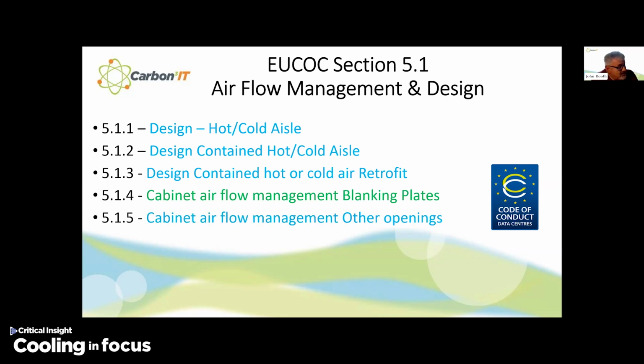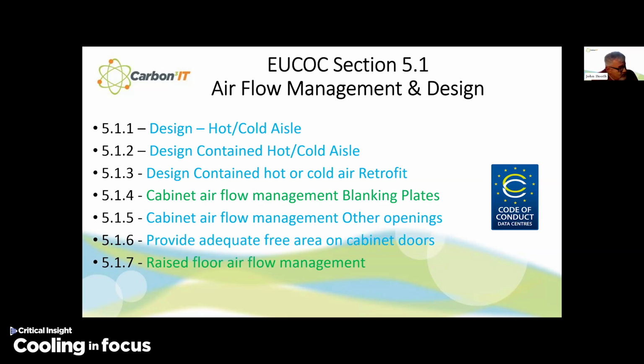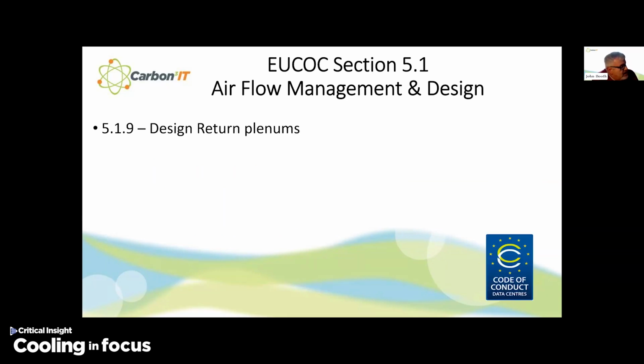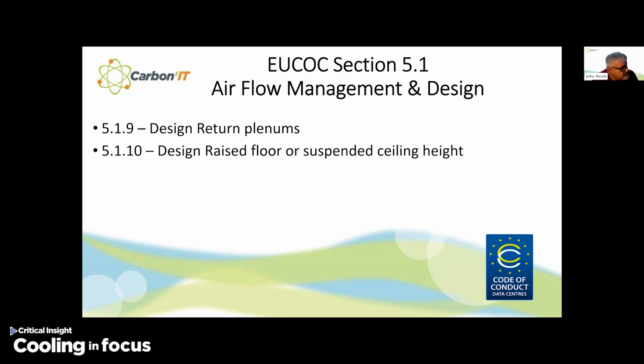Cabinet airflow management for other openings in your floor. Provide adequate free area on cabinet doors. Raised floor airflow management, and then raised floor airflow management in terms of obstructions. Design return plenums. So this would be ducting basically that goes from your hot aisle and directs the hot air straight into the top of the CRAC unit without hitting into the roof area.